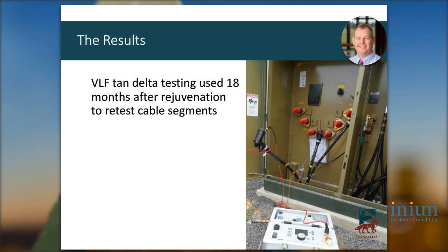What was surprising to us, but not to Novinium, was that at 6 months the tan delta results actually got a little worse—the cable appeared to continue degrading in insulation value. At 12 months it was back to where it was before injection, or a little better, and by 18 months it was testing like brand new IEEE cable, the kind you'd put in the ground and buy today.